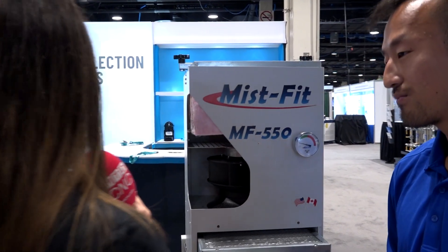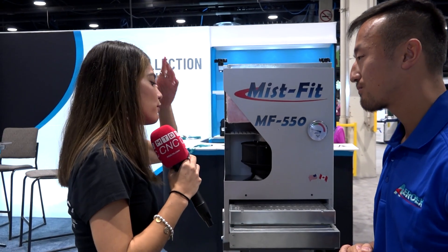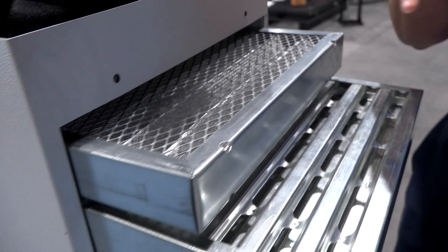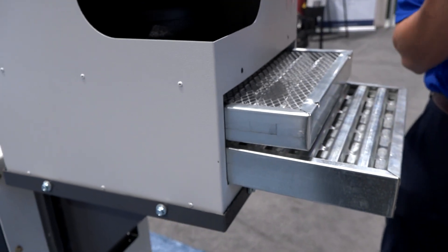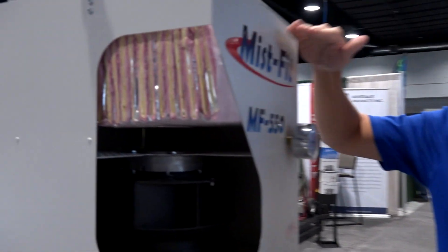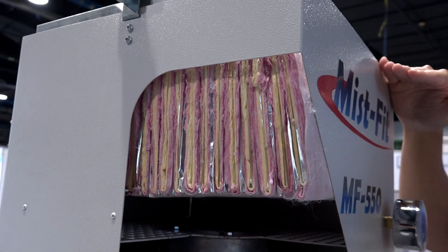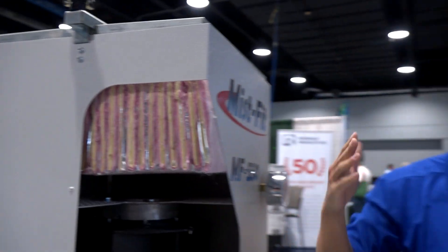In the Aero unit we saw before it had four to five stages depending on client requirements — how many stages do we have in the Mist-Fit? The Mist-Fit has three stages of filtration. The first two are non-consumable filters — mechanical elements that do most of the work. They form a fluid barrier so the coolant or oil coalesces into droplets and drops back into the machining cabinet. Anything else gets caught by our third stage filter, which is a fiber bed depth-loading filter with an average life of two years. This is the only consumable filter we have.